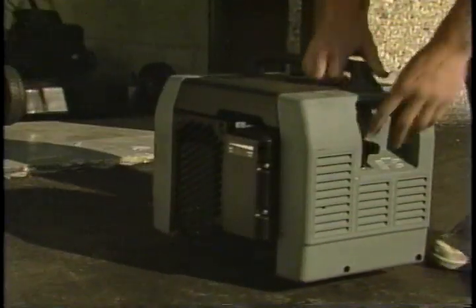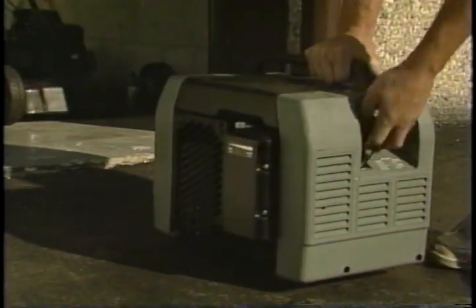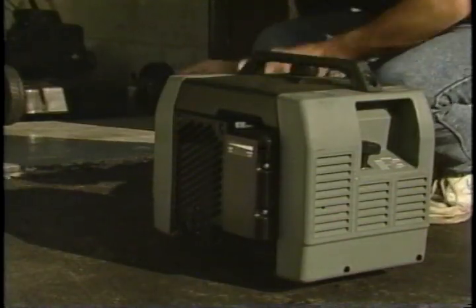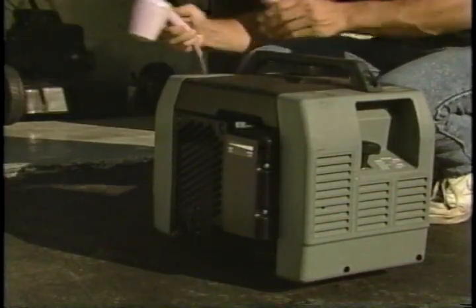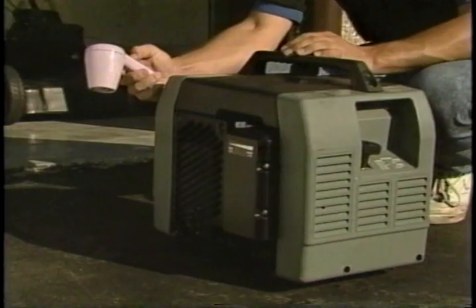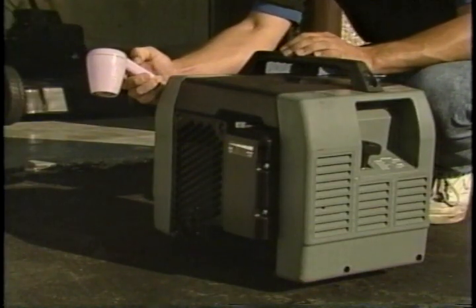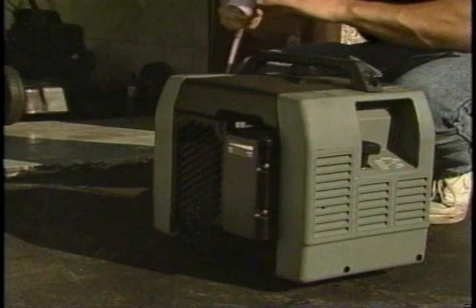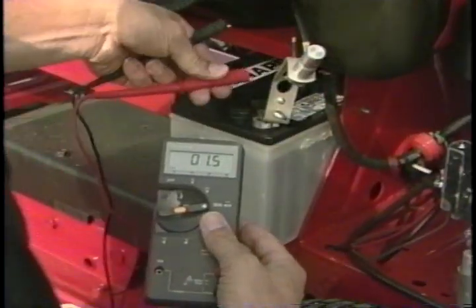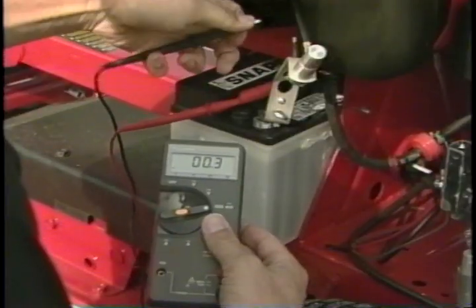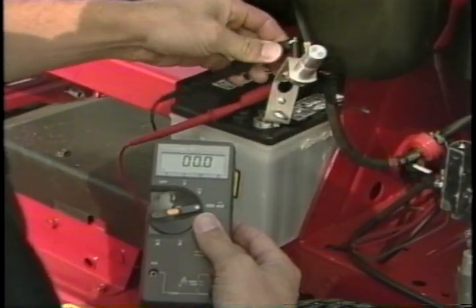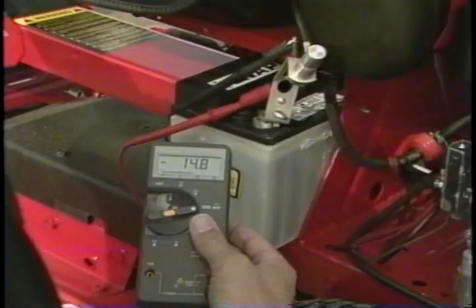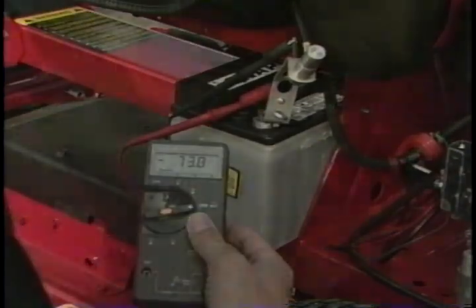To test small and medium-sized generators, use the generator to power a large heat gun or blow dryer. The 1500 to 2000 watts should load the generator enough for you to detect any engine anomalies as well as power availability. If you suspect a problem with the charging system of an engine, use a DC shunt to detect the charging rate of the system as well as current drain and starter draw.